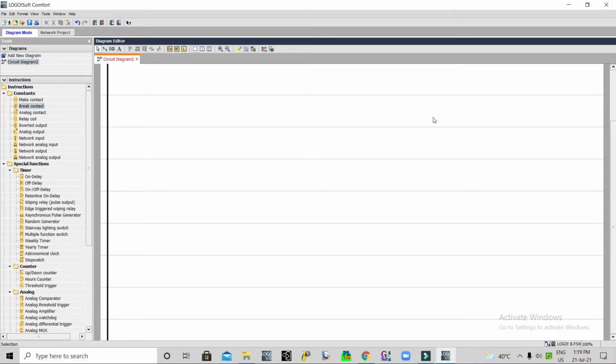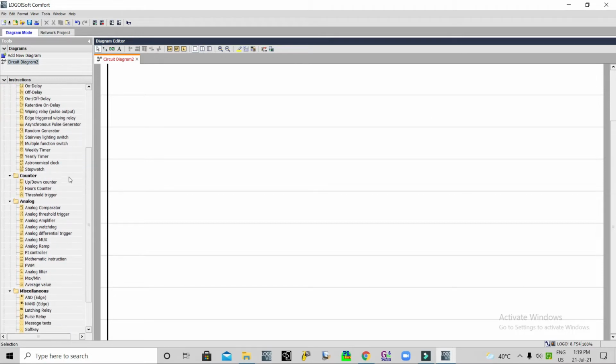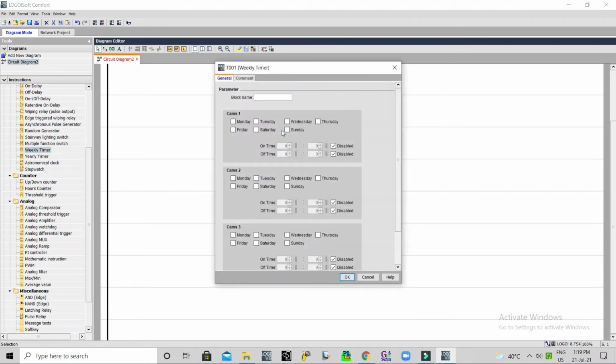We will see how we can do this program. First, we will configure timing. For 24 hours, I'm going to configure the timing for a 6 hour duty standby timing mode. The first AC will run 6 hours, then the second AC will run 6 hours, then the first AC will run again 6 hours. So each AC will run 12 hours per day, with 6 hour breaks.